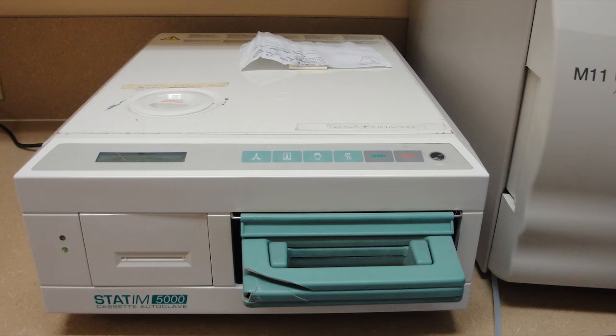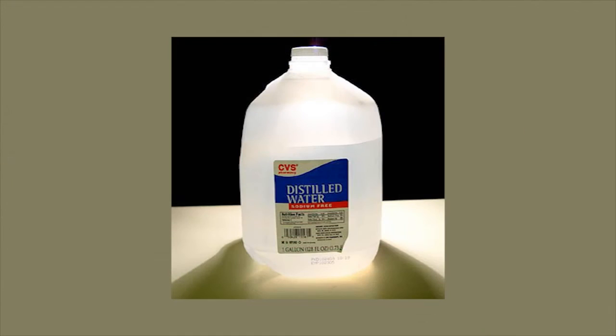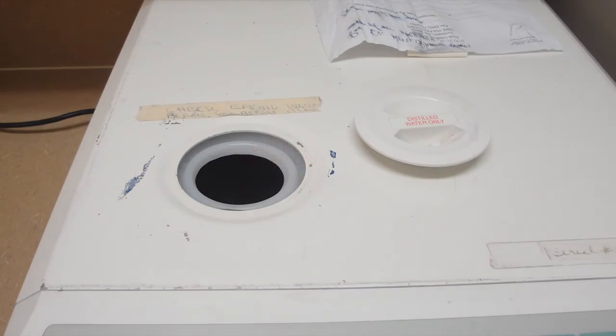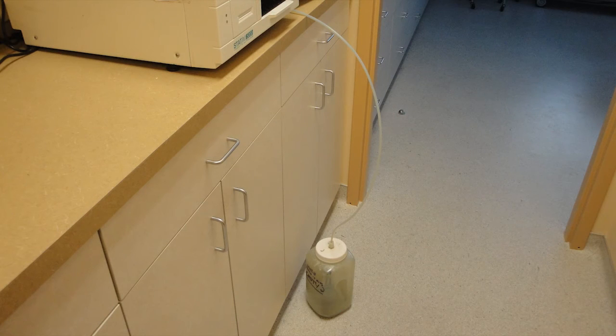There are different types of autoclaves that use different types of sterilization methods. Our machines rely on steam to sterilize our instruments. This being said, it is important that you understand these machines rely on distilled water to do their job. On the top of each machine, you will find an opening for the water reservoir. You will need to ensure that each machine has a full reservoir of distilled water so as to maintain proper sterilizing ability. Just as there is a reservoir of distilled water to do the sterilization, there is also a reservoir of distilled water that is left behind after the sterilization process is complete. This occurs as the steam that is evacuated from the chamber condenses back into a water form. You will need to make sure to check this reservoir frequently, which is found on the floor near the machine, so that it does not fill and overflow onto the floor, creating a water hazard.